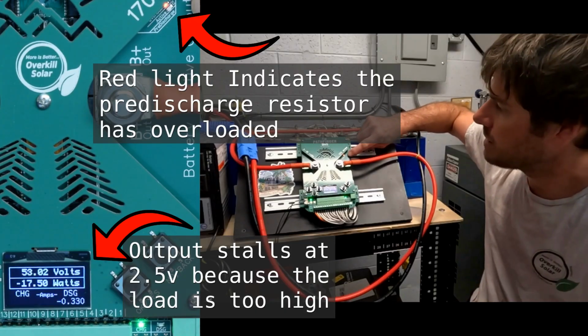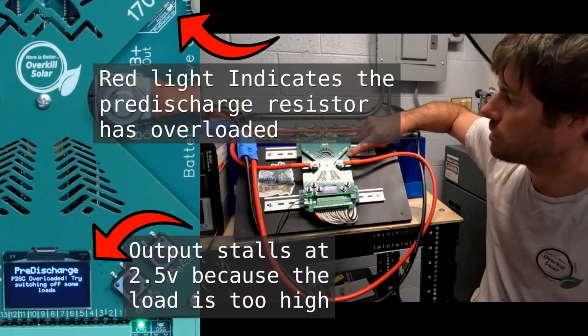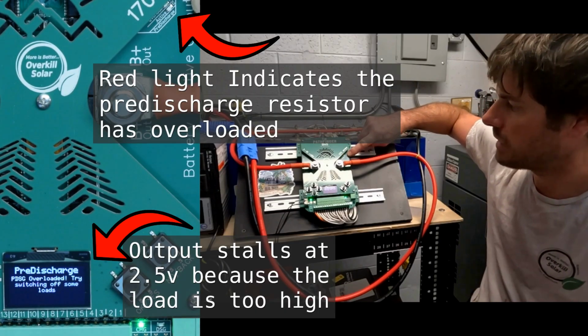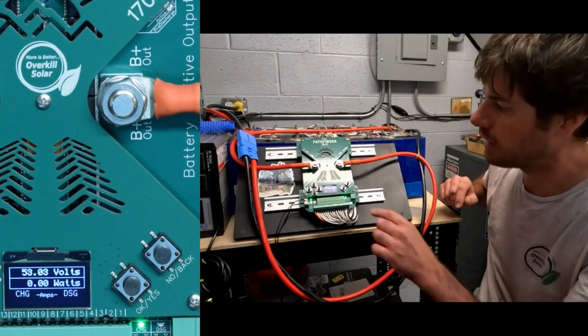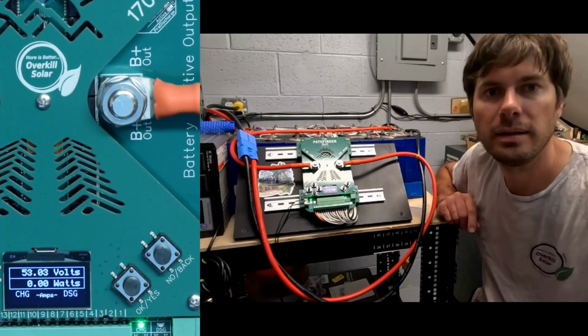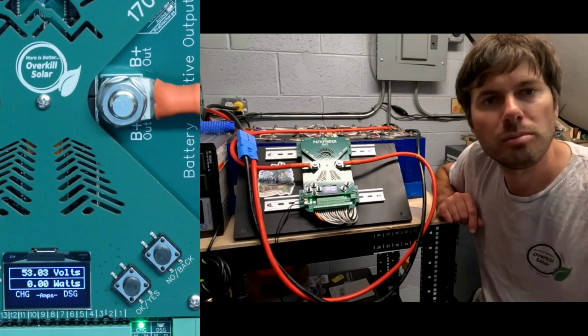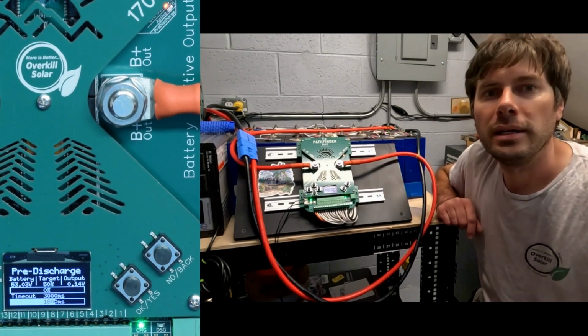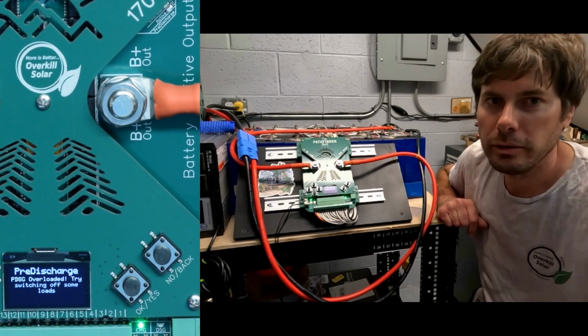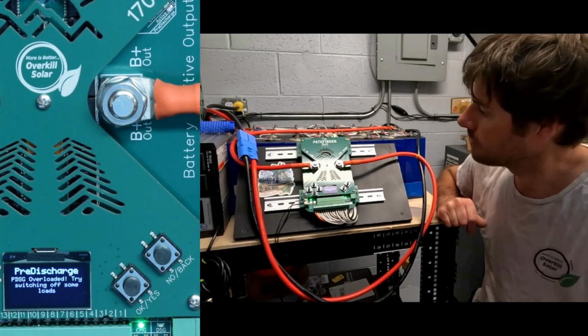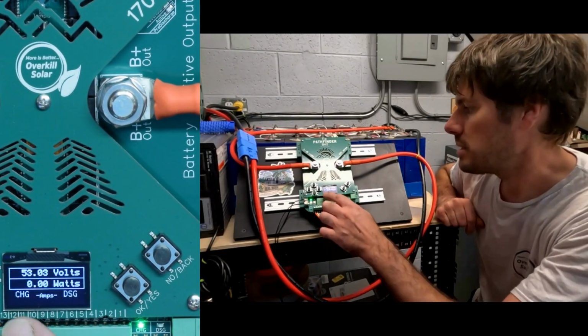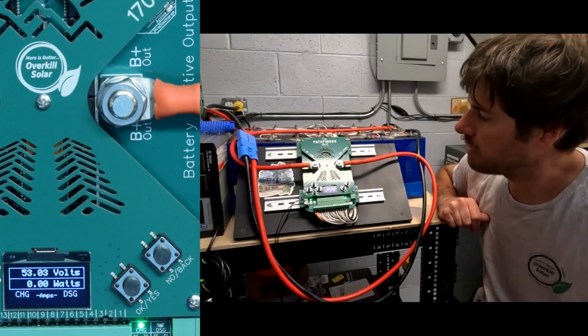Now what we saw is that the active light was very bright for about a full second, and then the overload light came on, and we got a warning that said pre-discharge fail. It's going to try again after the pre-discharge timeout, but it will fail again the same way until we remove the extra loads. It says pre-discharge overloaded, try removing the extra loads.